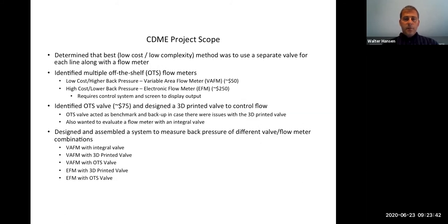Next slide, please. So we decided that the simplest approach is to put a flow meter and a flow control valve on each patient airline. The meter measures and displays the flow rate, and the valve lets us adjust it. This gives us the ability to indirectly control the volume of air going to each patient.